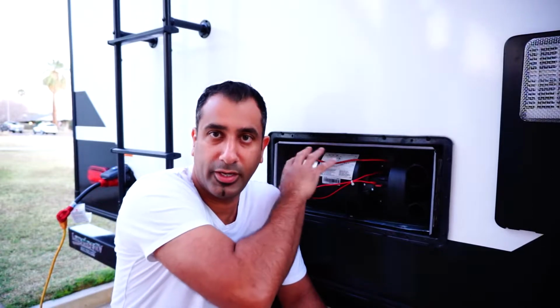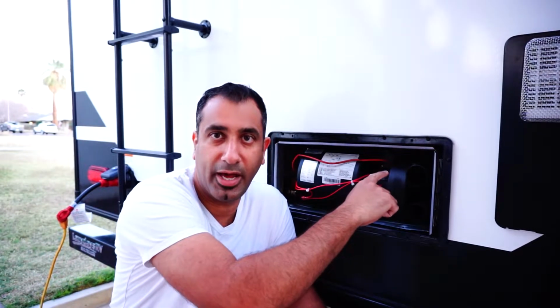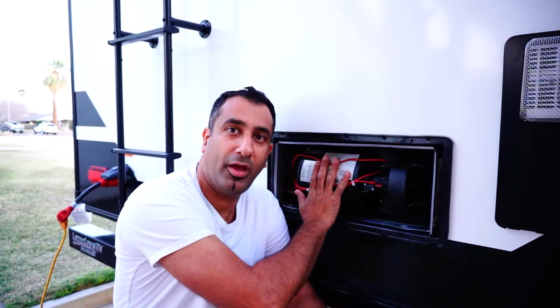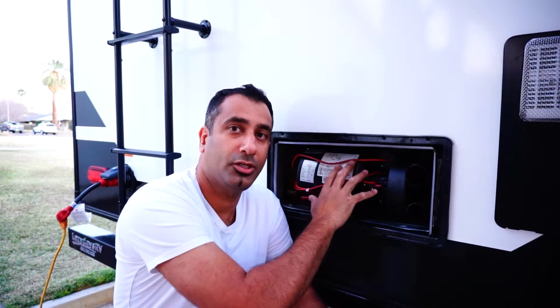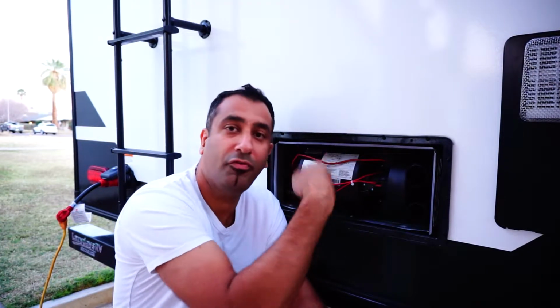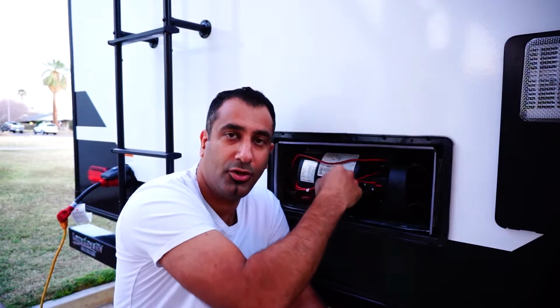The fourth thing is a faulty flame sensor. If the electrical board doesn't get a signal from the igniter, and usually in small furnaces the igniter and the flame sensor are the same thing, then it turns off the gas flow, and that could also cause a short cycle. Less common reasons could be the blower not pushing enough air, so many technicians will check the RPM, how fast the blower is turning to push air through the furnace to the ductwork. And a less common thing is a damaged heat exchanger.